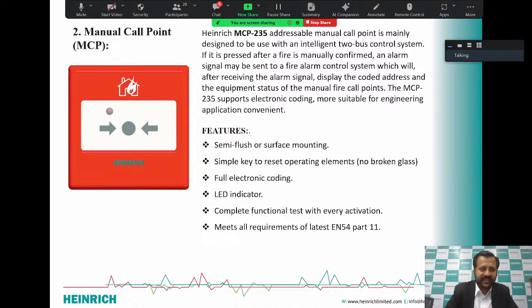So this is the manual call point. If we have a key to open it, to reset it, and if we have a plastic lid over it, you just open it and press it. So the manual point will start its work and give a signal to the fire alarm panel, and the hooter will start giving the siren. It is semi-flush or surface mounting, whichever way you want to install it. It has an LED indicator and full electronic coding. As you can see, there is no need of breaking the glass. It has a plastic lid over it. You just pull it or open it and then press this white area. So the signal will be given to the fire alarm.